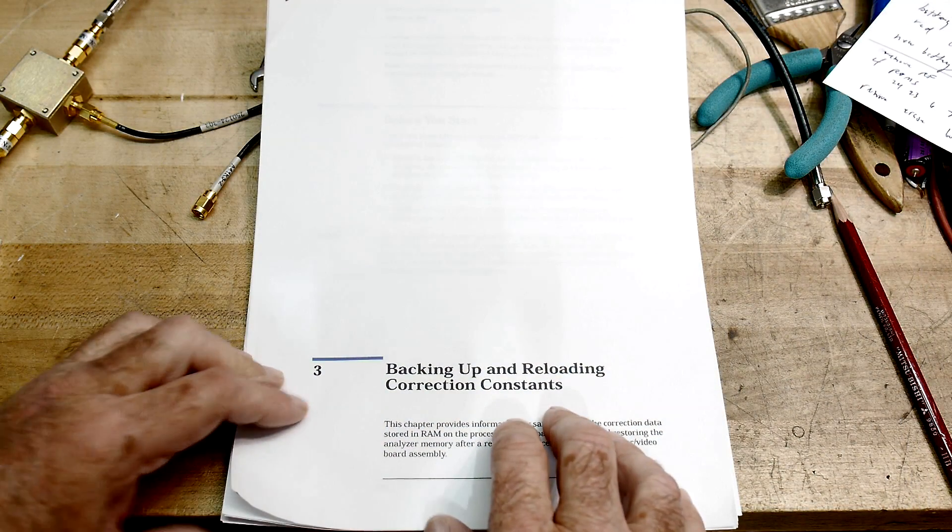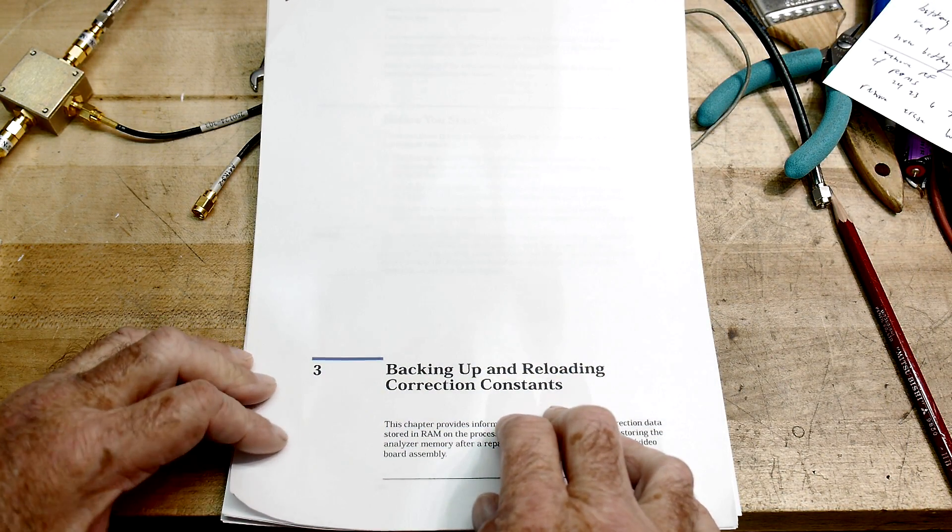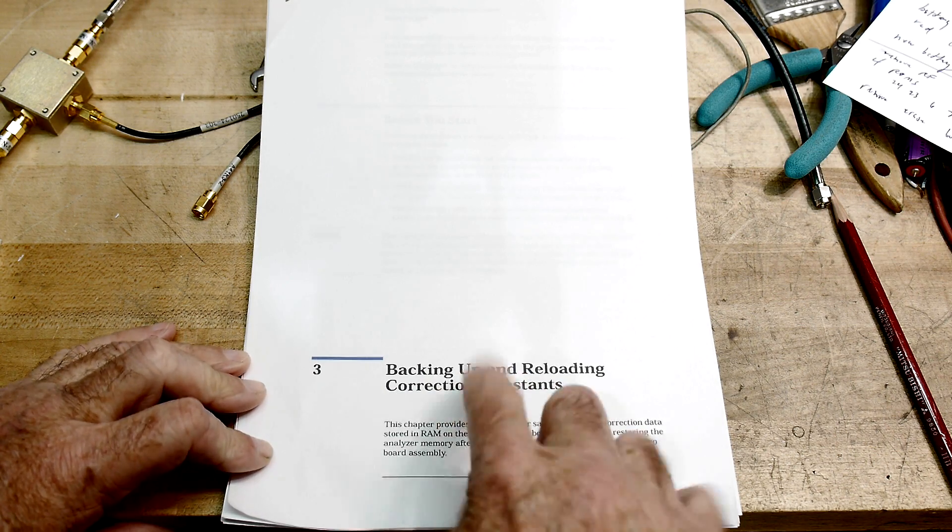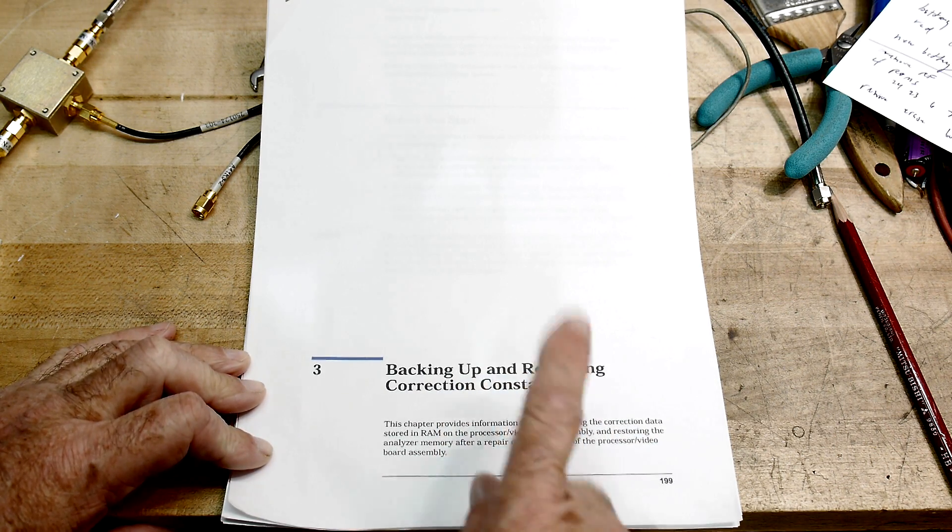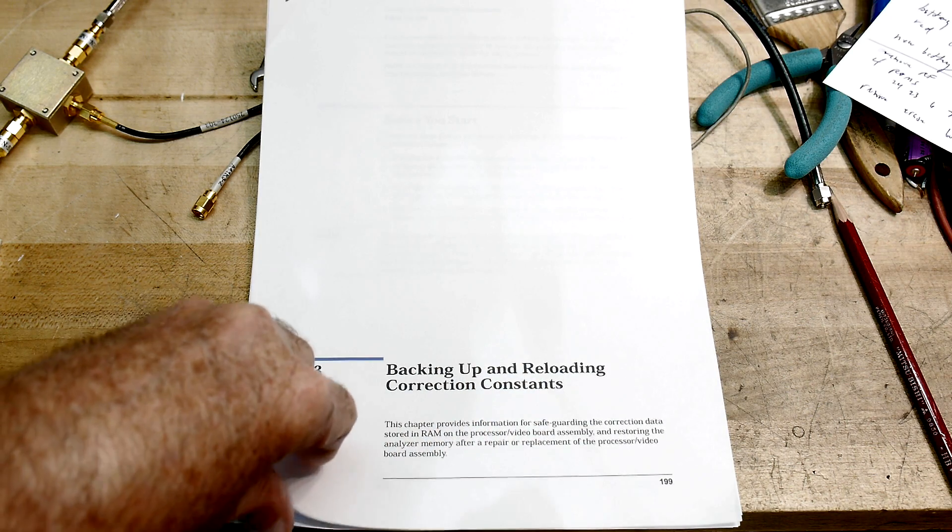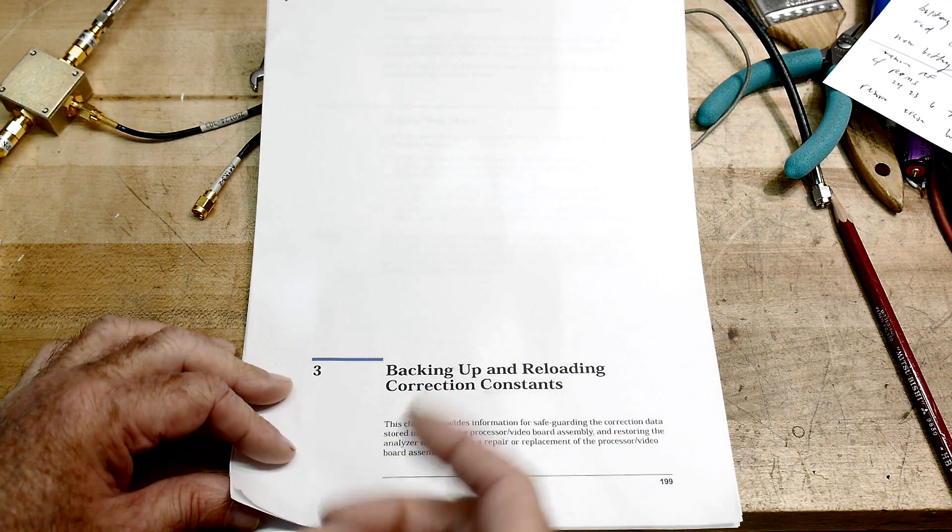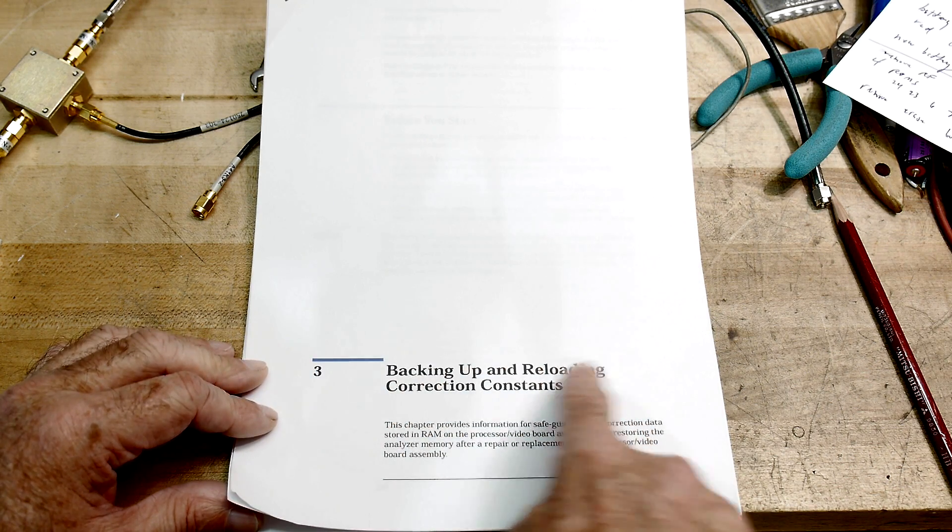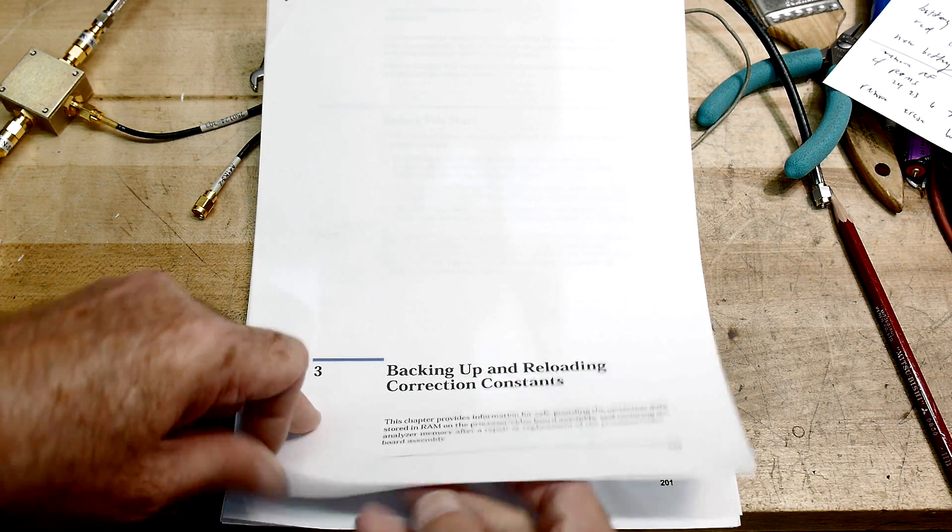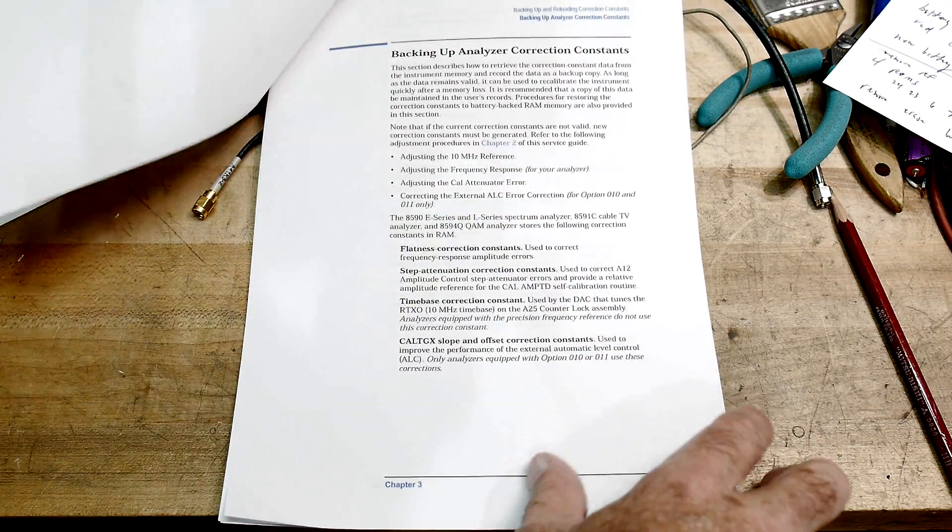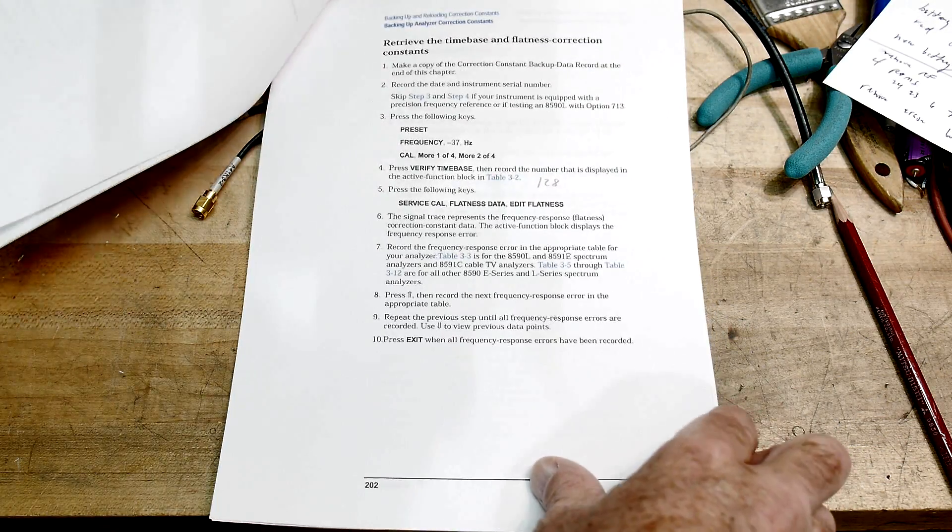So there is a calibration manual for this spectrum analyzer. I think this is out of the CAL guide, not the user guide, but the CAL guide. There's an actual big thick manual on calibrating the instrument, and this is chapter three, backing up and reloading correction constants. So if you get one of these, please go through this procedure. It tells you step by step what to do.